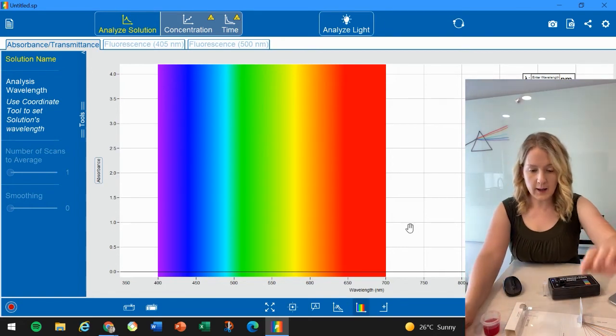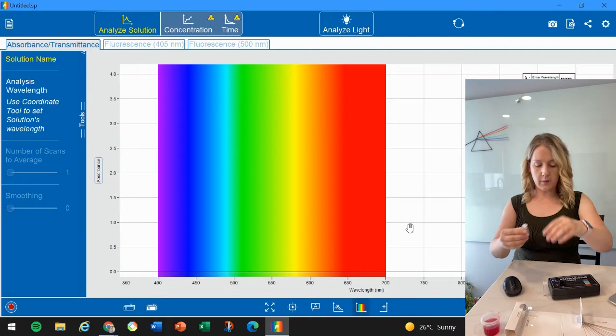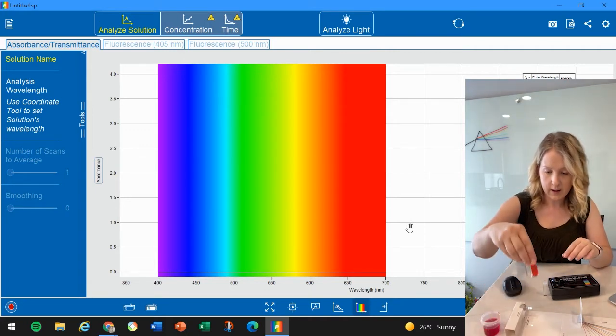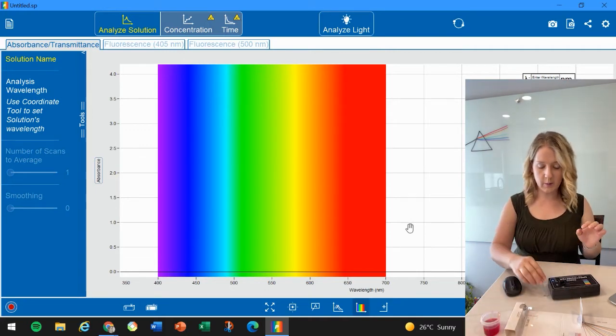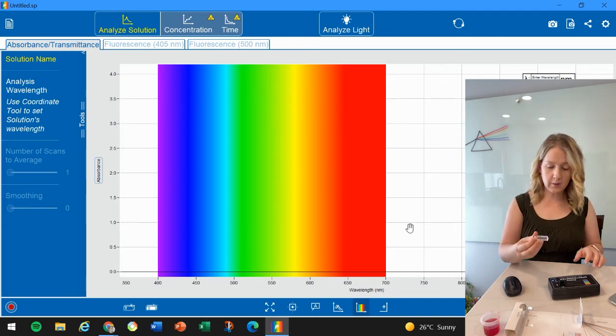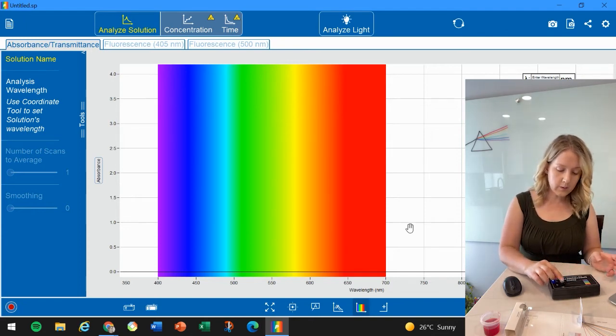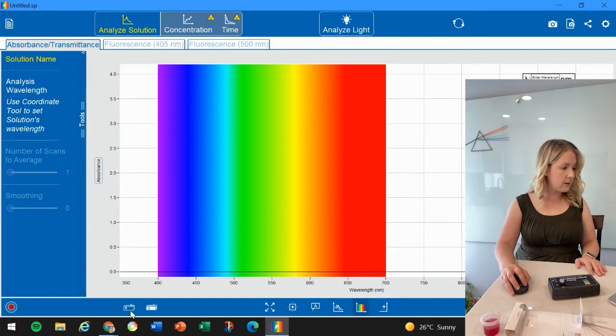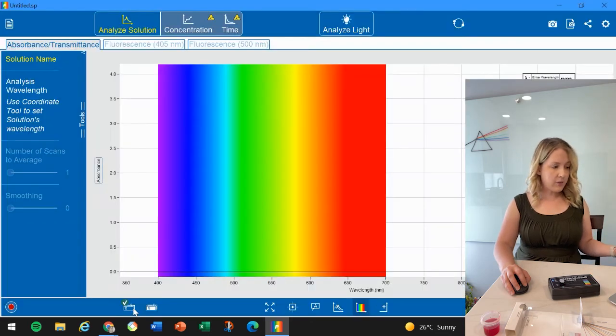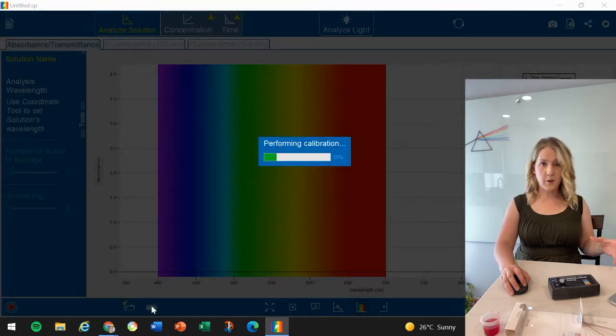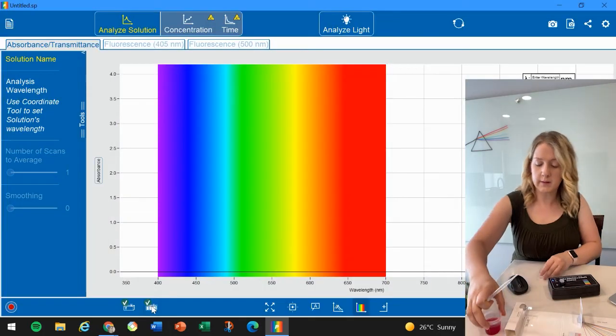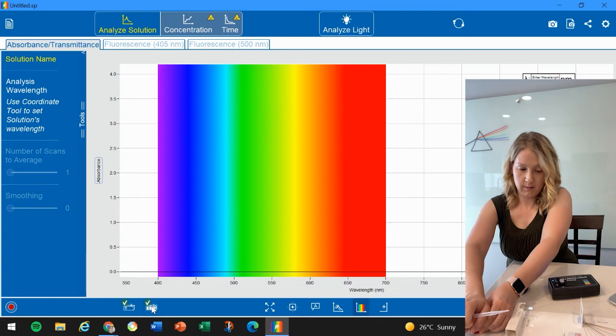And instead I have the cuvettes here. I've replaced the cuvettes that are with this separate one with the ones that are specifically for Pasco. So I'm going to place a cuvette of water into the spectrometer, and here I'm just going to calibrate it for dark and calibrate it for light. And this basically just removes the water's absorption from the data so we can get more accurate data from the cuvette full of this red dye.